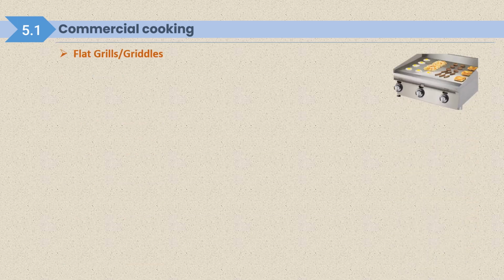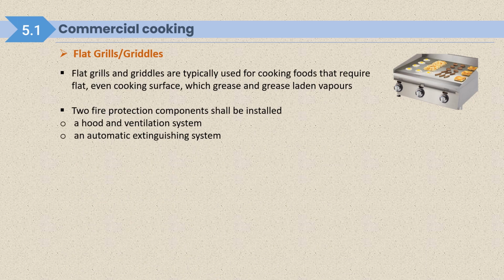In commercial cooking, there are other appliances also mentioned, like flat grills or griddles. Flat grills and griddles are typically used for cooking foods that require a flat, even cooking surface, with grease and grease laden vapors. Two fire protection components shall be installed: a hood and ventilation system, and an automatic extinguishing system. So whenever we are using flat grills and griddles, we should always use them under the hood and ventilation system only. It will have an automatic fire extinguishing system also installed.